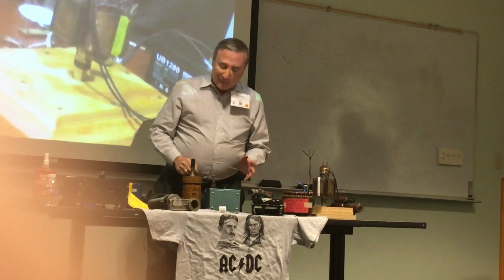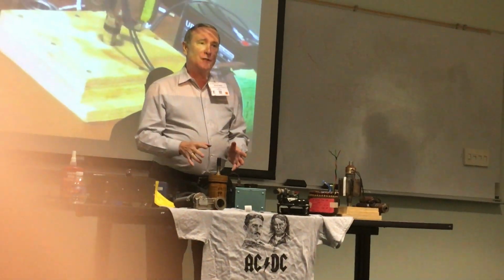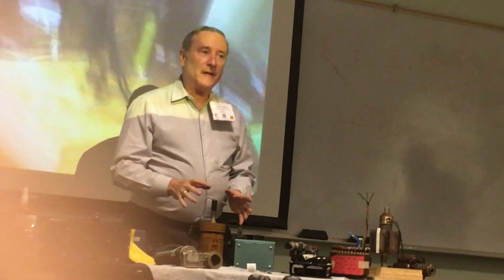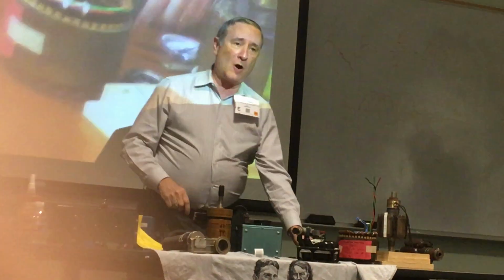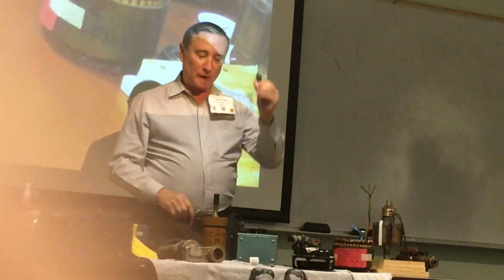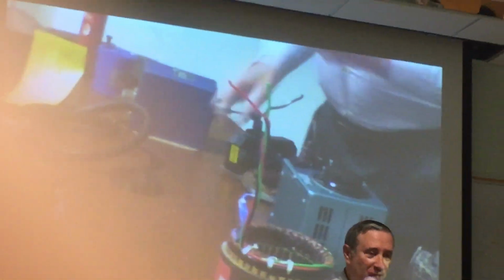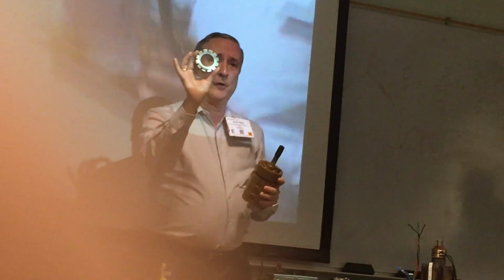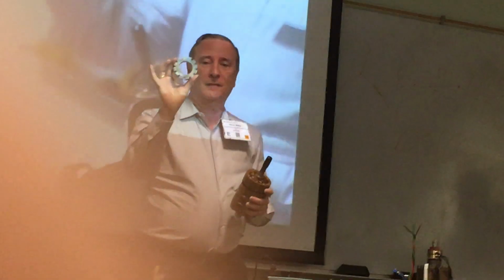Let's see. That's a brush type generator. Then the Westinghouse engineering people figured out how to make a generator without the carbon brushes, so they can run the generator a lot longer. What they designed was a three-stage generator. Here's the rotor out of a brushless generator. There's a circular 14-pole magnet, and it's attached to the rotor. They both turn.